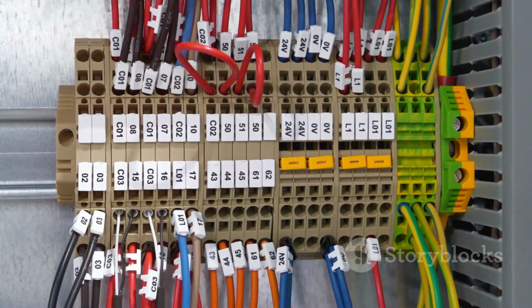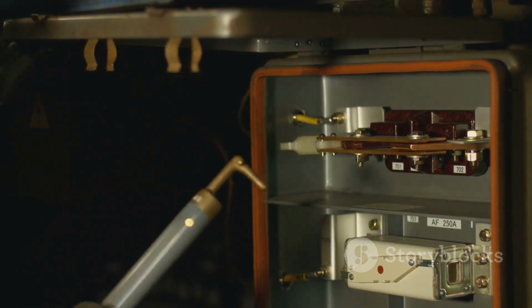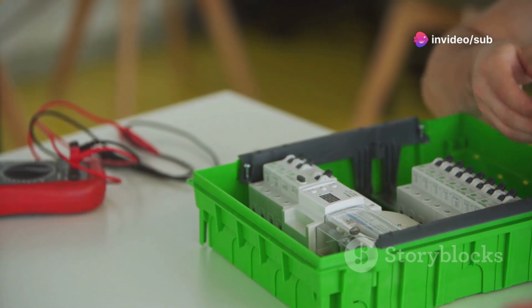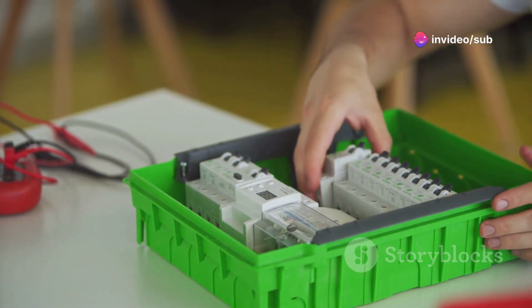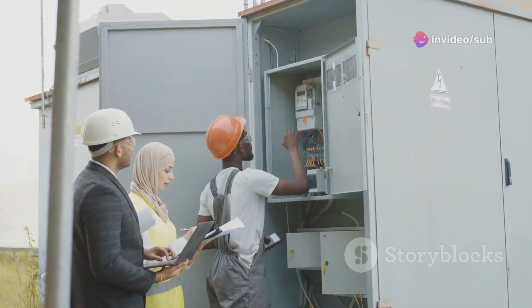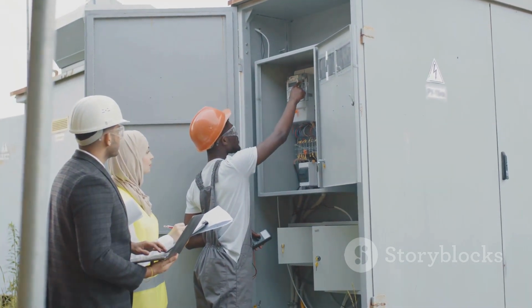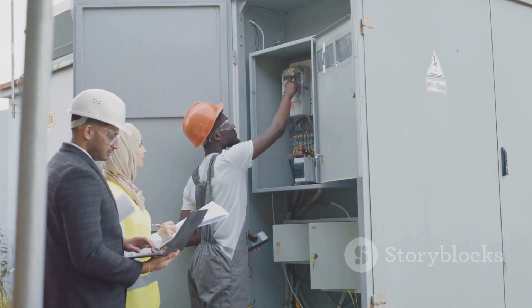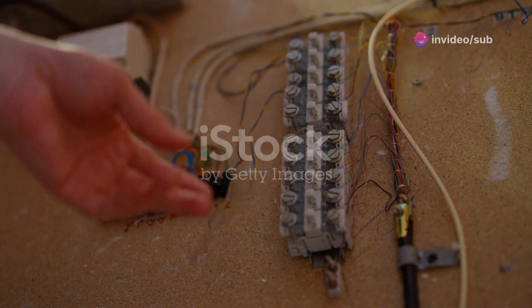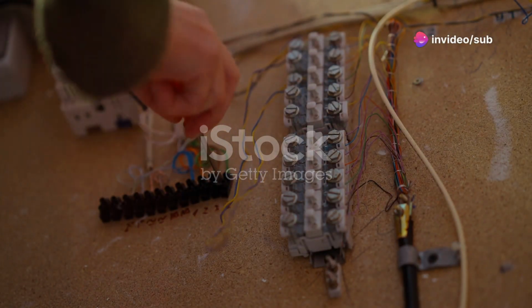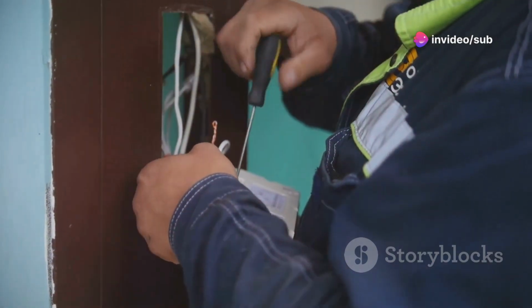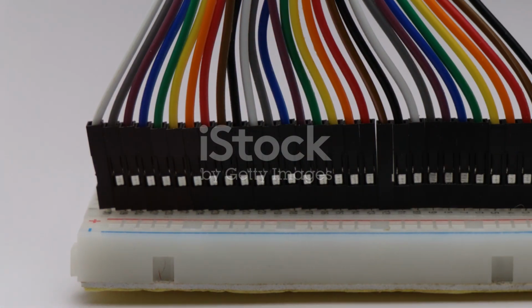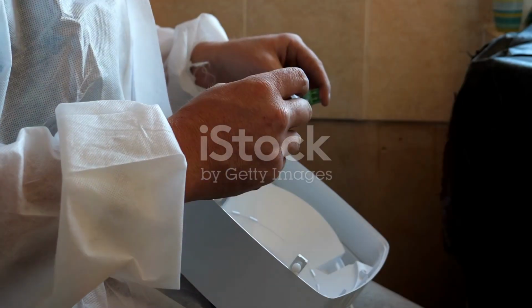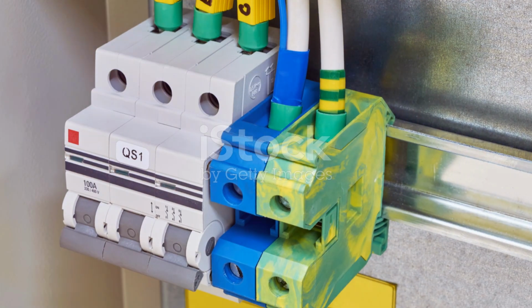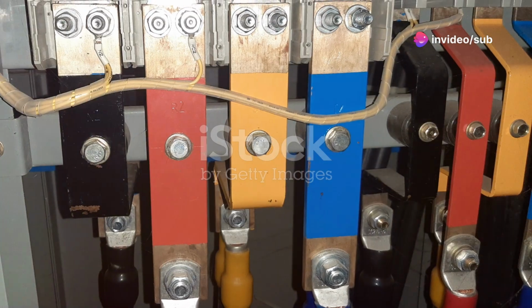Second, wiring flexibility. In tight panels or when adding new circuits, multi-terminal breakers let you connect wires without overcrowding one terminal. It saves space, reduces clutter, and makes future maintenance easier. Third, busbar integration. Some breakers are designed to connect directly to a bus bar and also to a branch circuit at the same time. For example, one terminal may clamp onto the bus bar, while another accepts a wire, making installation faster and more secure. These features make multi-terminal breakers a smart choice in complex or busy panels.